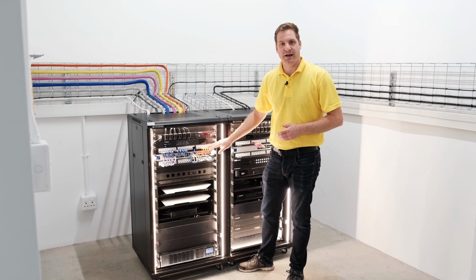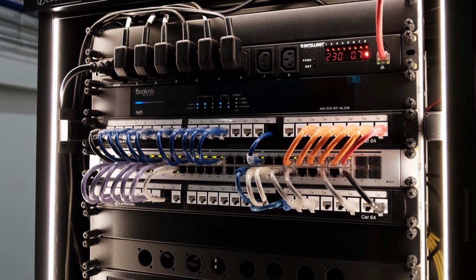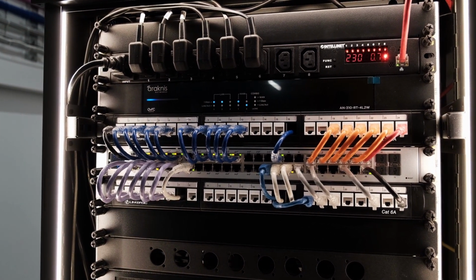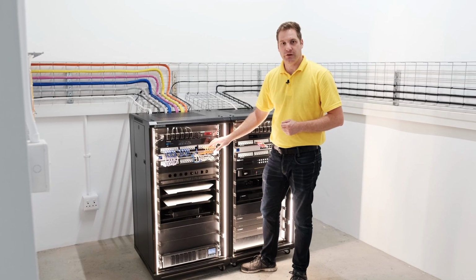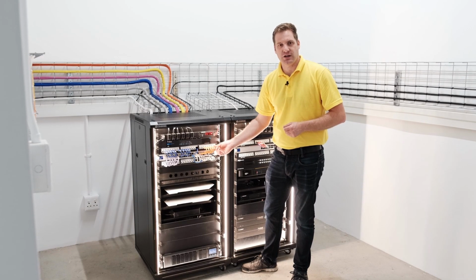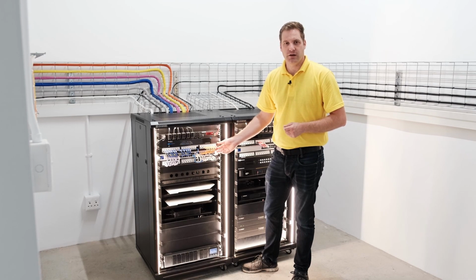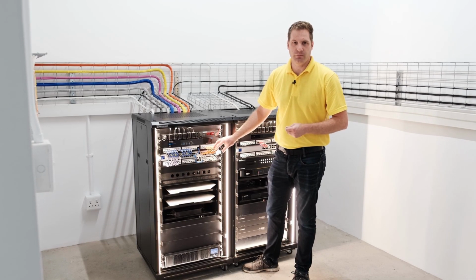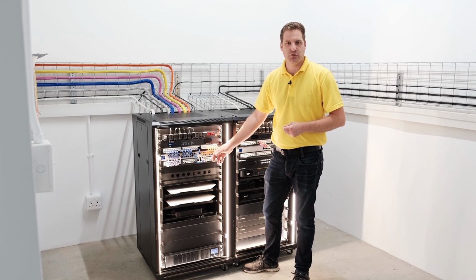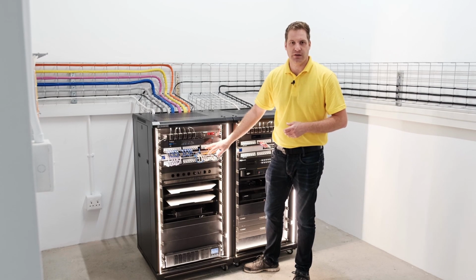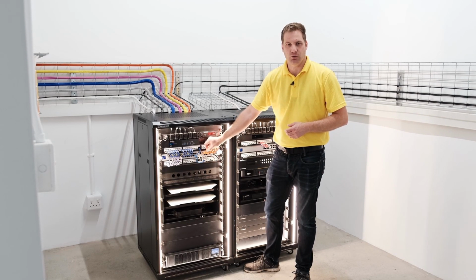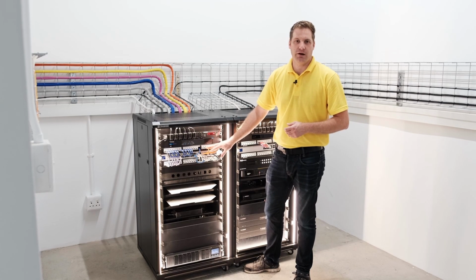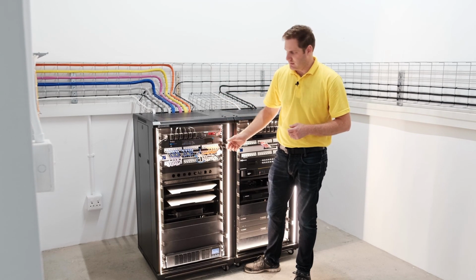Beneath that we have what we call a patch panel, where all the cables from the cable tray terminate. These cables are fixed in place, with only the patch cables on the front removable. This is for longevity of the cable—if the cables went straight into the network switch, there's an opportunity for wear and tear. It's much easier to replace a small patch cable than repair one fixed in place from the house.